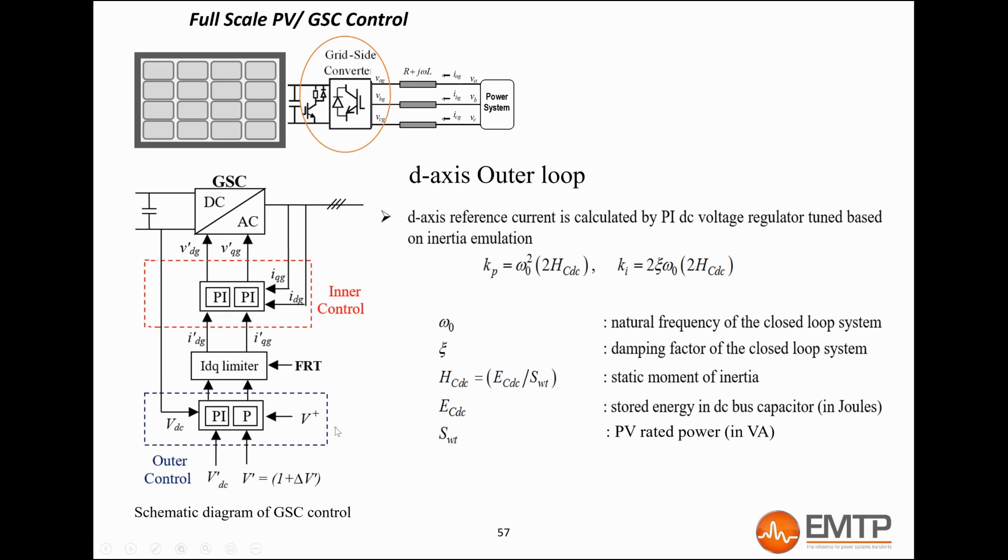Two level control loops are utilized. On the D-axis, the outer loop regulates the DC bus voltage to its reference value. The output of this loop is the D-axis current reference, which will be the reference for the inner loop.